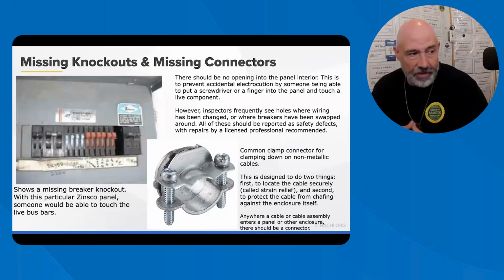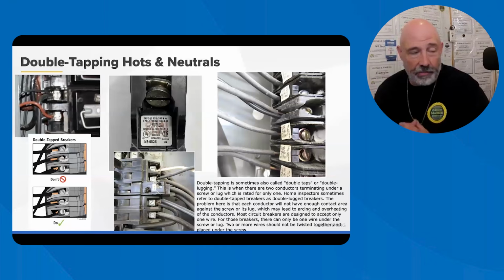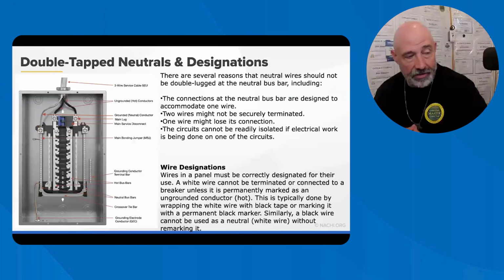If you see these Zinsco panels, a lot of times those are not going to be insurable. So call those out. And there is a list of panels that are not good. A lot of times what I'll do is I've got a website for that and I'll throw that in my inspection report just so customers have it. Anyways, double taps, you don't want to see any double taps. Remember, Cutler-Hammer and Square D are the two where you can actually double tap. Here, double tapping neutrals and designations.